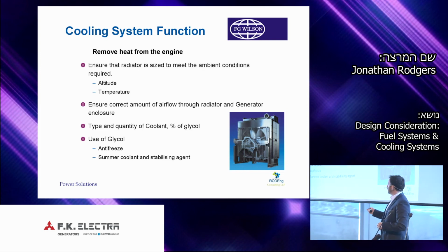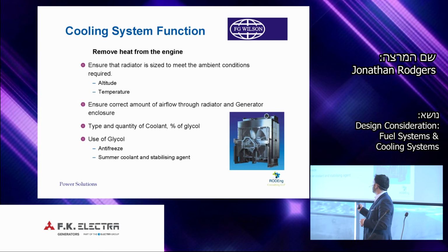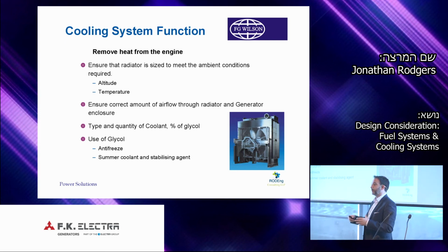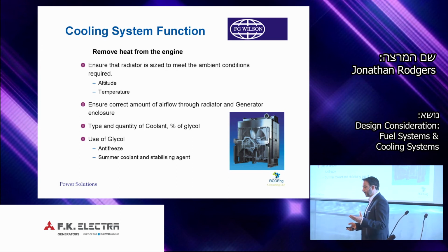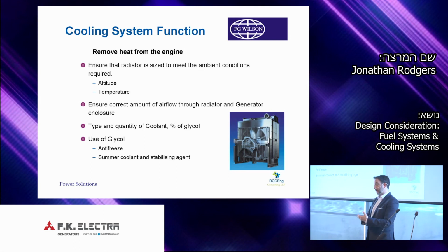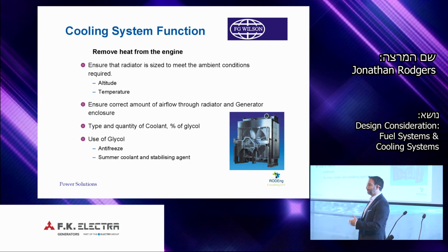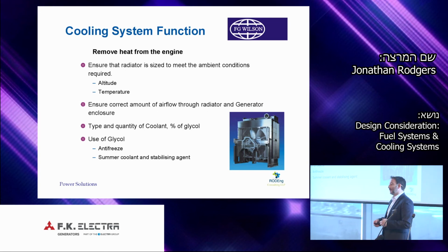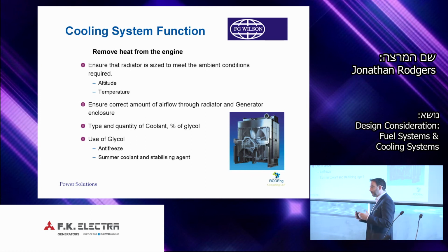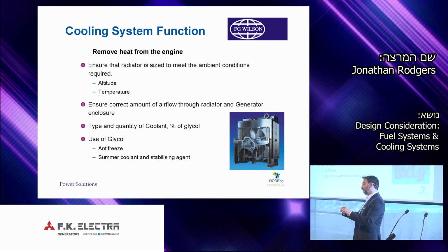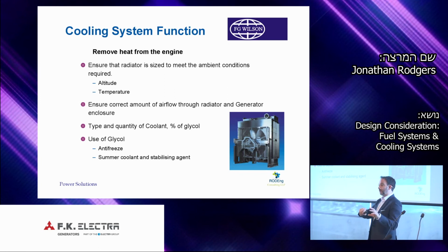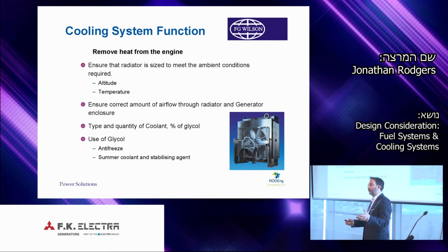In sizing all of the flow and size of the radiator, we need to look at the type of coolant we use and what percentage glycol concentration. And you will notice through all of our FG Wilson range, we have a standard glycol requirement, more commonly known as antifreeze. So you may think you won't have a lot of frost in this area for a lot of the time, but you will see the same glycol concentration recommended for here and for hotter countries as you will for what we'll have in the UK and even Northern Europe.